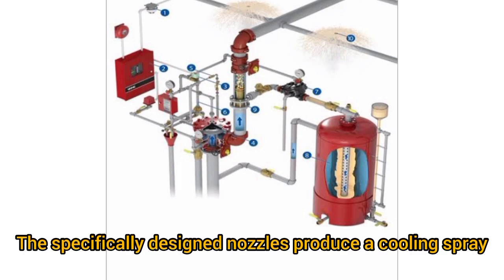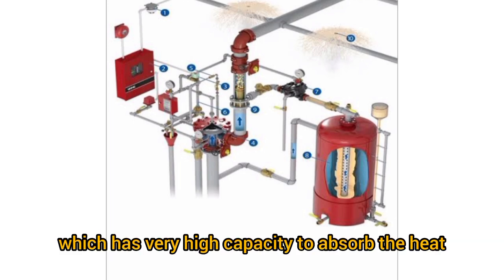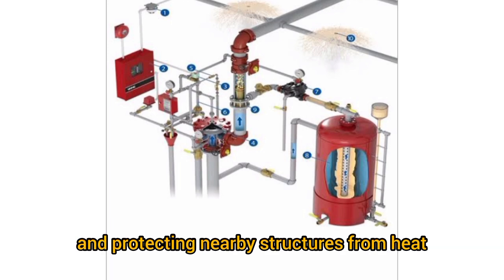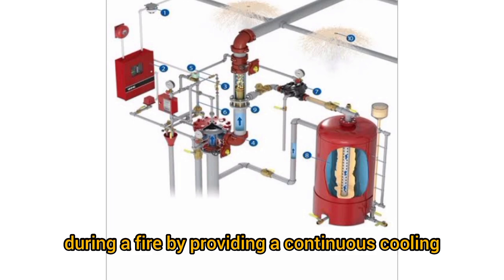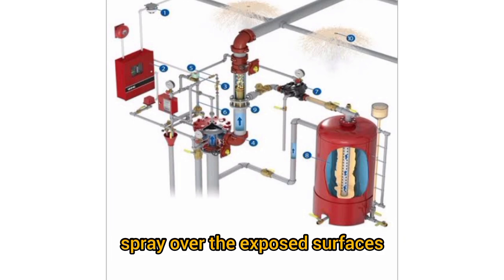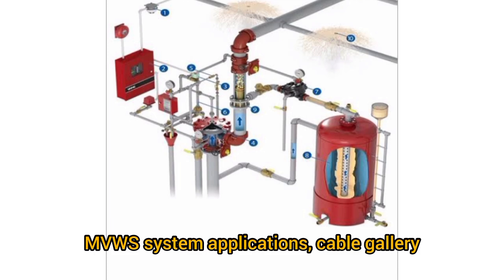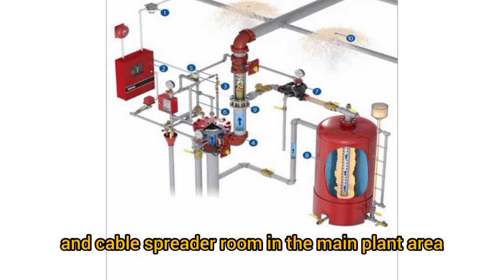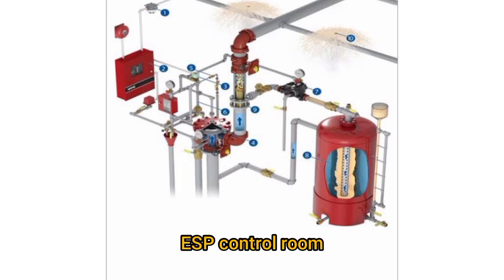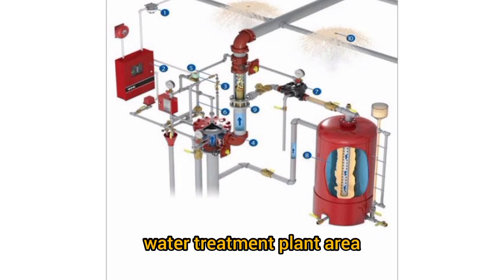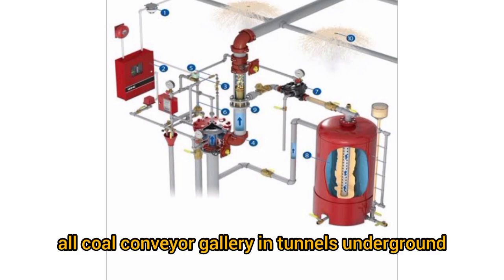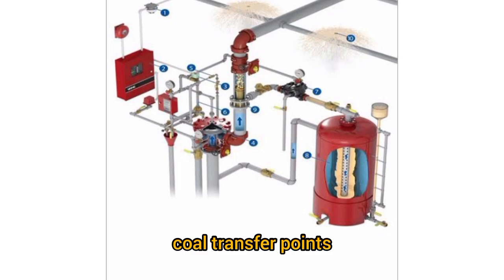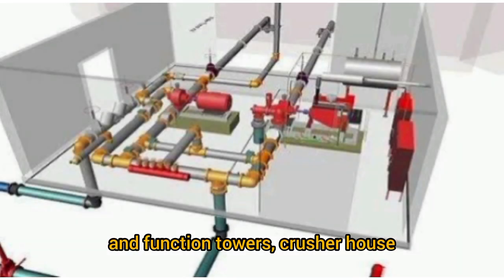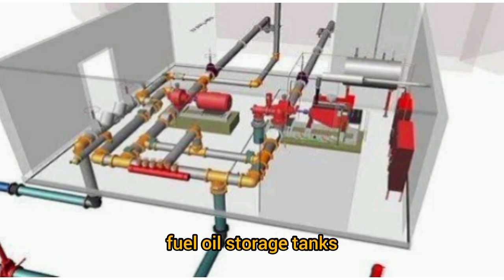The specifically designed nozzles produce a cooling spray which has very high capacity to absorb heat, protecting nearby structures from heat during a fire by providing a continuous cooling spray over the exposed surfaces. MVWS system applications: cable gallery and cable spreader room in the main plant area, ESP control room, switch yard room, ash handling plant area, coal handling plant area, water treatment plant area, fuel oil pump house, loading and unloading areas, all coal conveyor galleries in tunnels underground and above ground, coal transfer points and junction towers, crusher house, emergency DG building, fuel oil storage tanks.